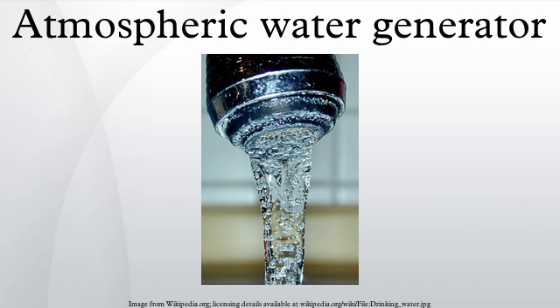In a cooling condensation-type atmospheric water generator, a compressor circulates refrigerant through a condenser and then an evaporator coil which cools the surrounding air. This lowers the air temperature to its dew point, causing water to condense. A controlled speed fan pushes filtered air over the coil. The resulting water is then passed into a holding tank with a purification and filtration system to help keep the water pure and reduce the risk posed by viruses and bacteria collected from the ambient air on the evaporator coil. The rate at which water can be produced depends on relative humidity, ambient air temperature, and the size of the compressor.